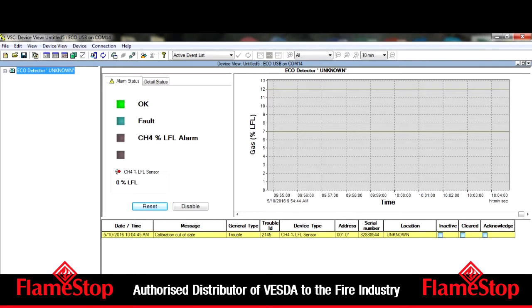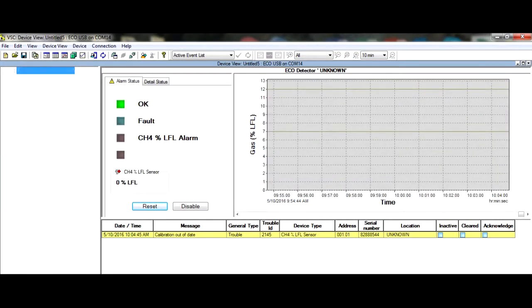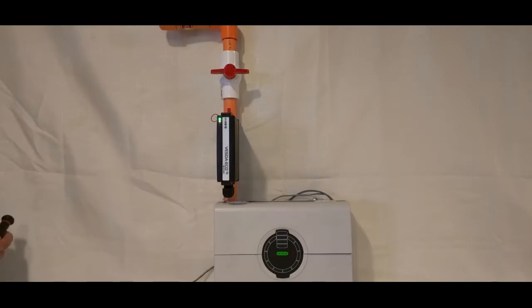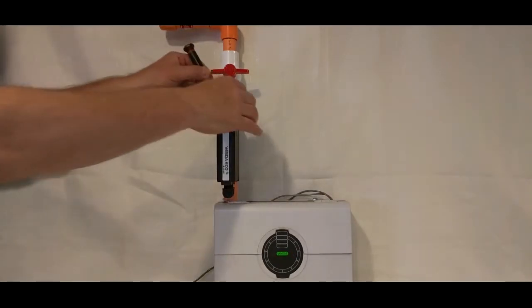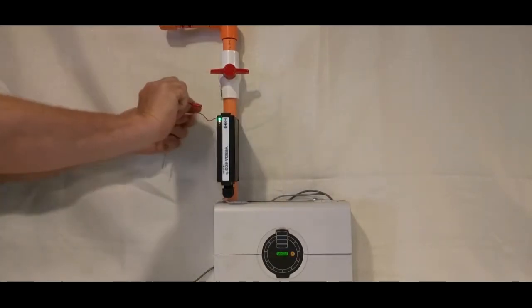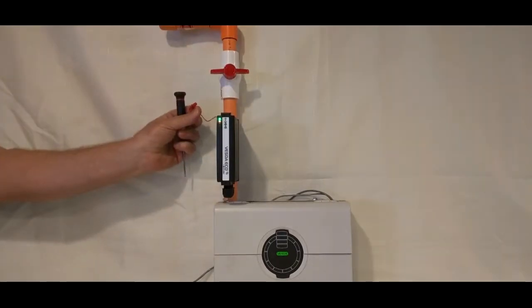Note the calibration fault shown in the event log. Ideally, the ECO detector should be calibrated before the calibration due fault occurs. Using a small flathead screwdriver, depress the compression ring and remove the calibration port plug.